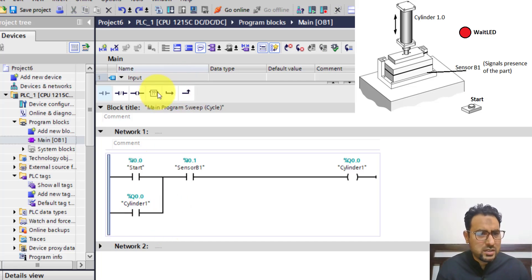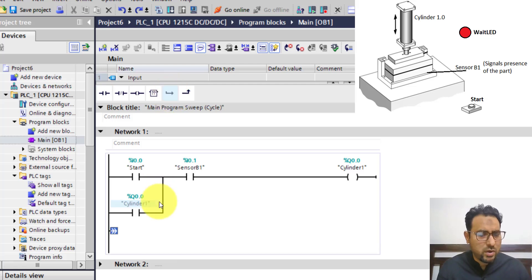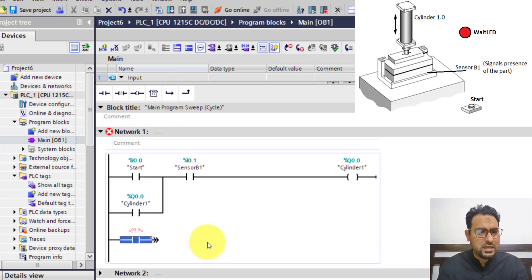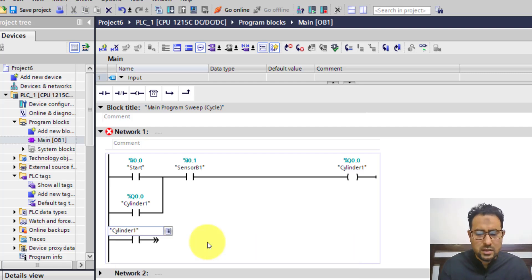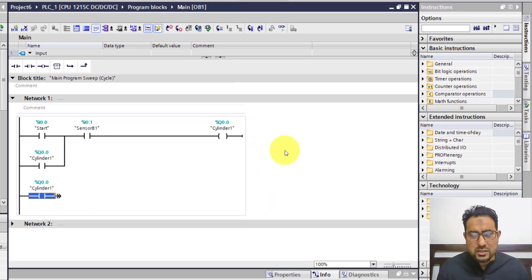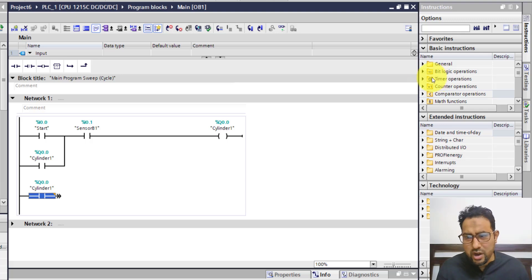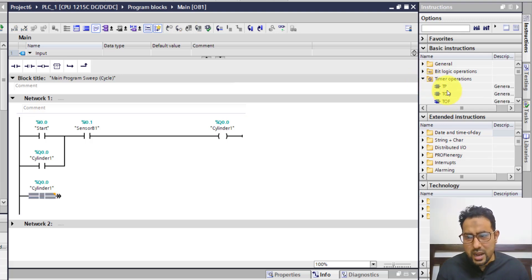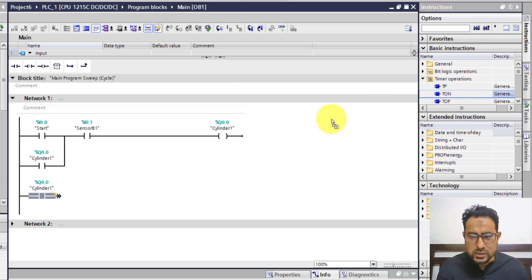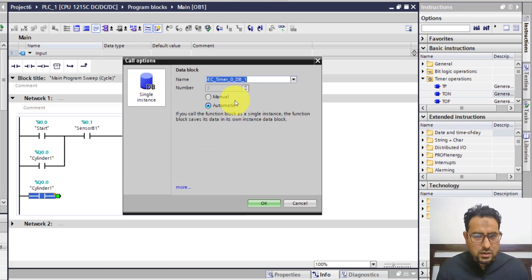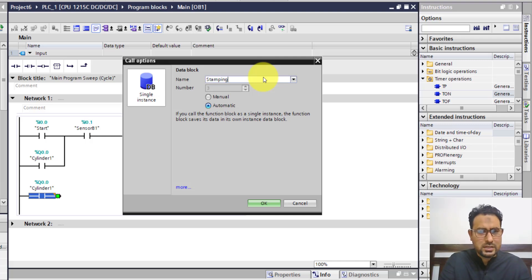Once cylinder 1 is on, I want a timer to run as well. So on a new rung, if cylinder 1 is on it will turn on a timer. For the timer, you can go to basic instructions and drop down the timer operations menu — you can see timers there. I'm going to use the T-On timer. Click and drag it to place it where you want. You can name this timer — I'll call it stamping timer.